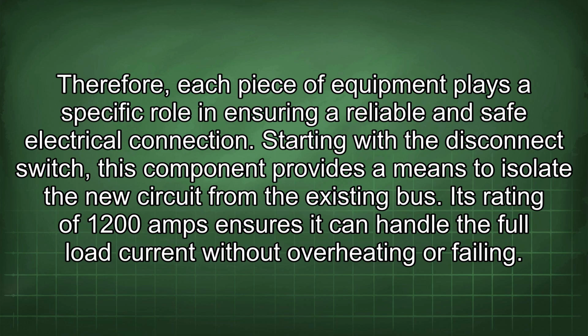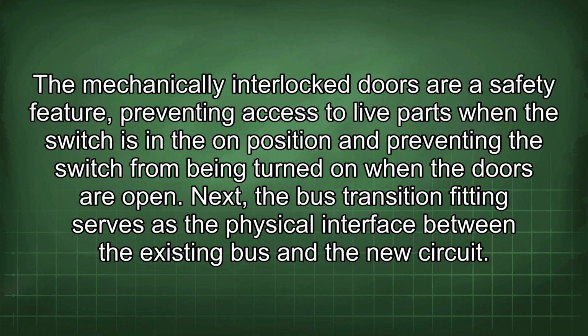Starting with the disconnect switch, this component provides a means to isolate the new circuit from the existing bus. Its rating of 1200 amps ensures it can handle the full load current without overheating or failing. The mechanically interlocked doors are a safety feature, preventing access to live parts when the switch is in the on position and preventing the switch from being turned on when the doors are open.